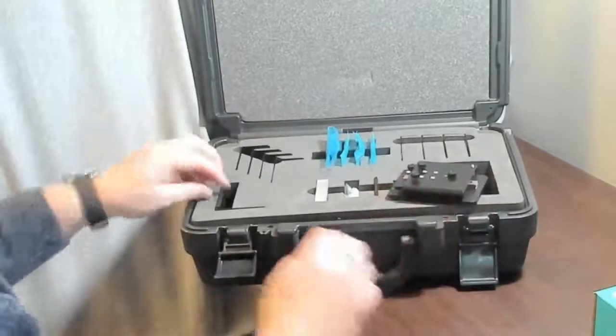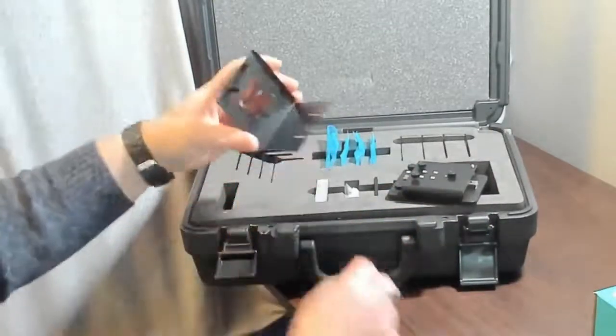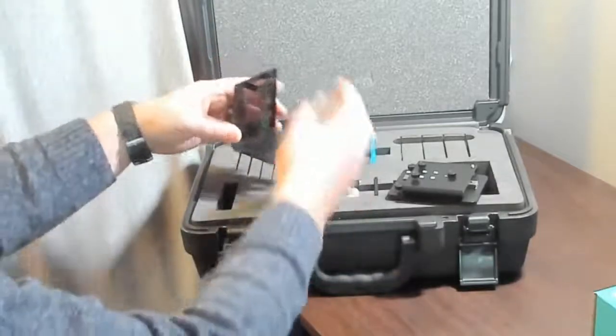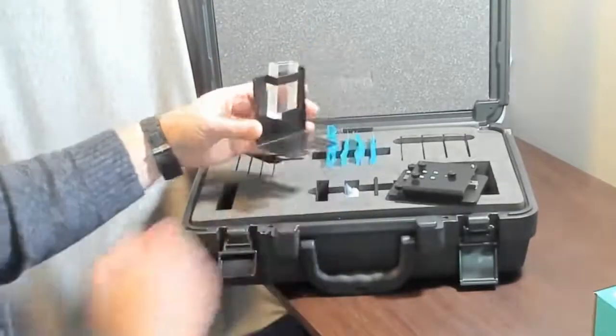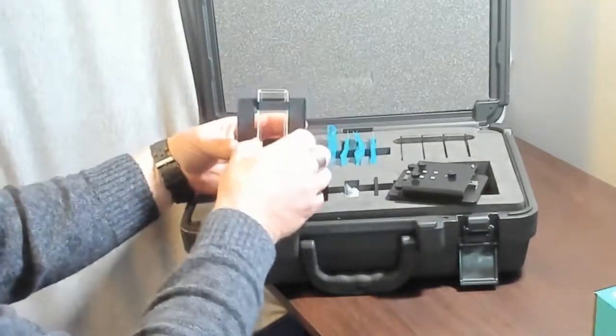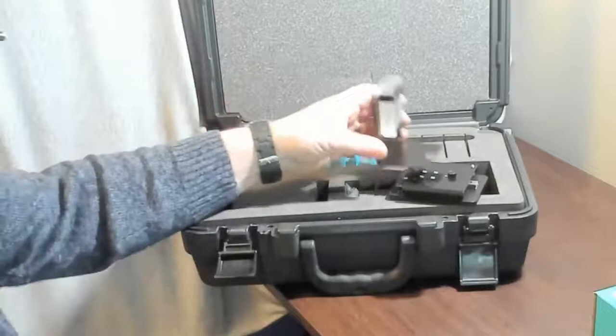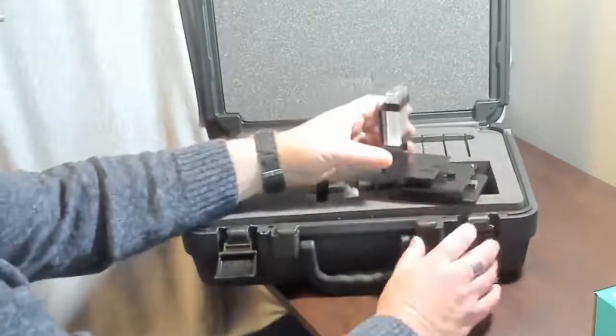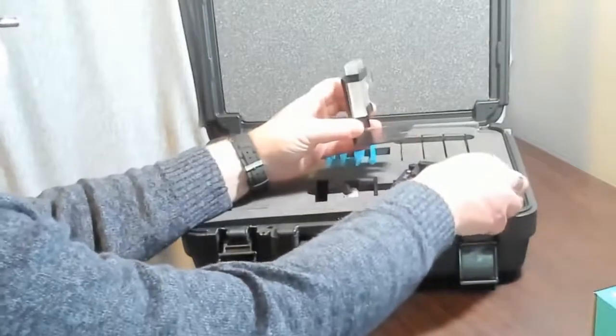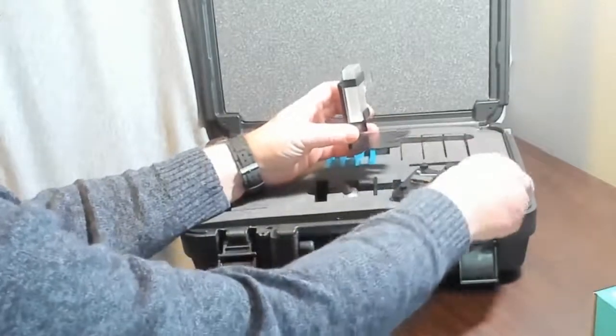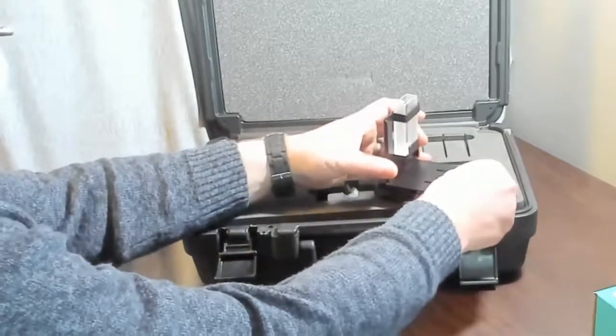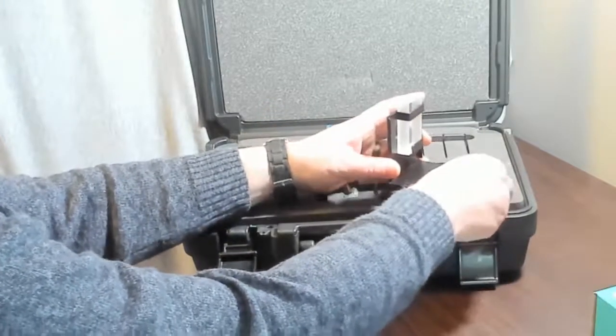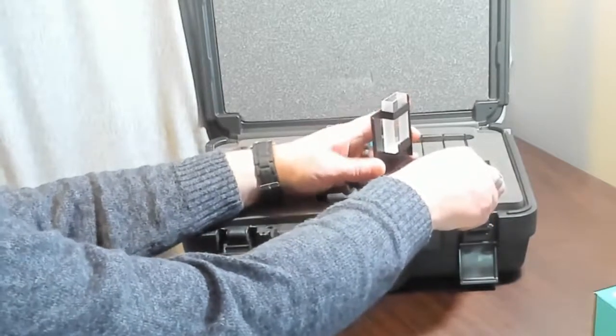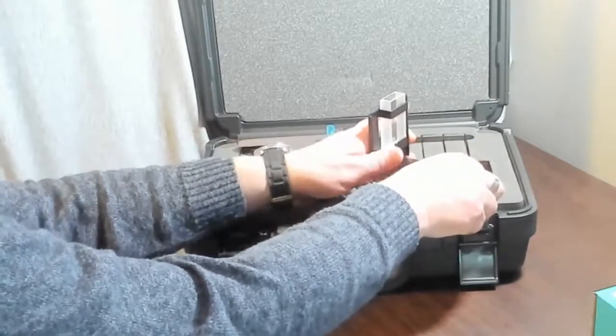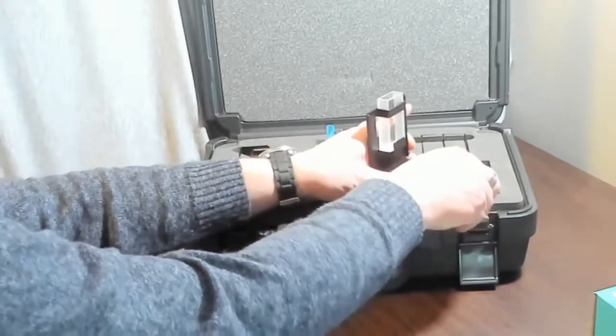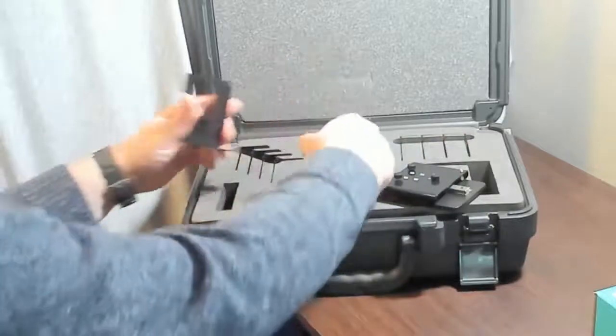So essentially, if I'm going to do liquid measurements, I would take this piece, which you can see is made with a spot to hold the cuvette. Whoops, helps if I load it correctly. In place. This would attach via these little thumb screws right here to that device, and then this is spring loaded to slide things back and forth. So if I need to slide it out to pull the cuvette away, the spring will cause this to come up against a stop where we know we're in the same place every time for a measurement. Okay, so that's for measuring liquids with a cuvette.